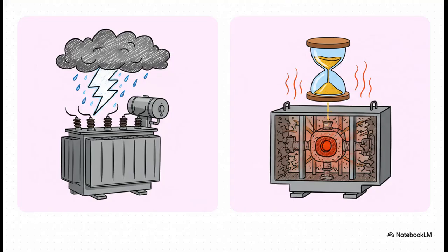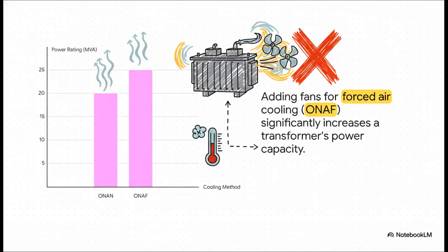The threats they face really fall into two main camps. You've got your external faults. These are the big, dramatic events like a lightning strike or a massive power surge. But the more sneaky threats are the internal faults. These are the slow burn problems: insulation breaking down over years, the oil inside getting contaminated, or the most common culprit, simply overheating. And this chart shows just how important cooling is.